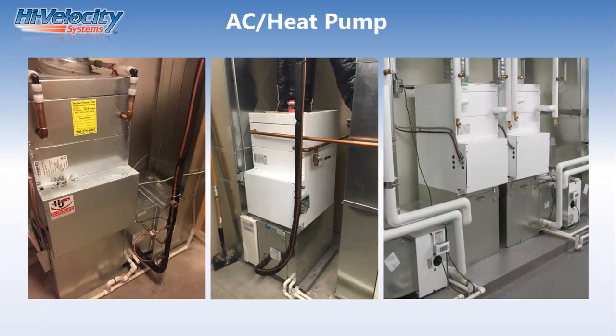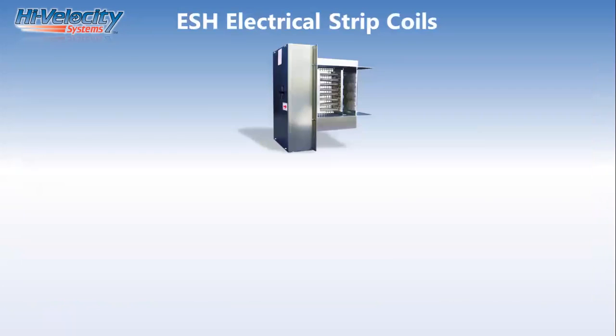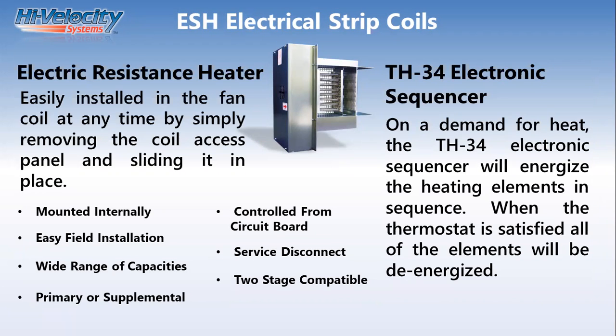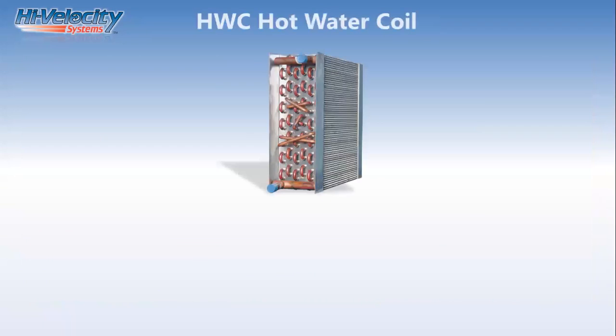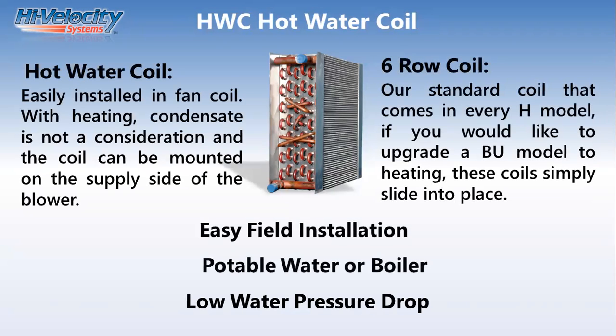Now, when we talk about heat pumps, in most northern climates, a heat pump isn't going to be able to heat 100% throughout the year, and there needs to be some sort of backup auxiliary heat source. We do have multiple options for that, one being an electric strip for electric resistance heat that slides into the air handler, basically creating an electric furnace that is available in fixed, also modulating panels from 5 to 25 kilowatts. Most of what we elect to do, because of the proven efficiency, is hydronic hot water heating as either primary or auxiliary backup heat source.